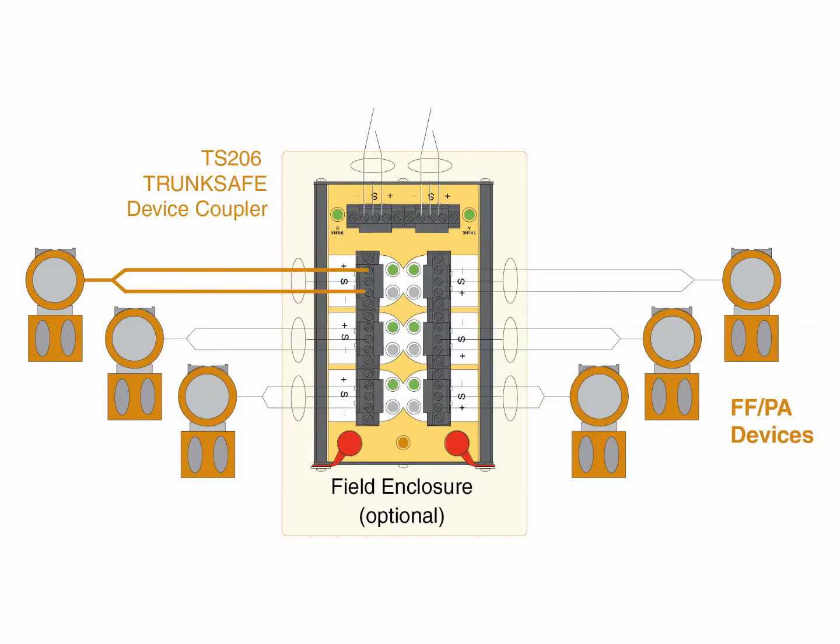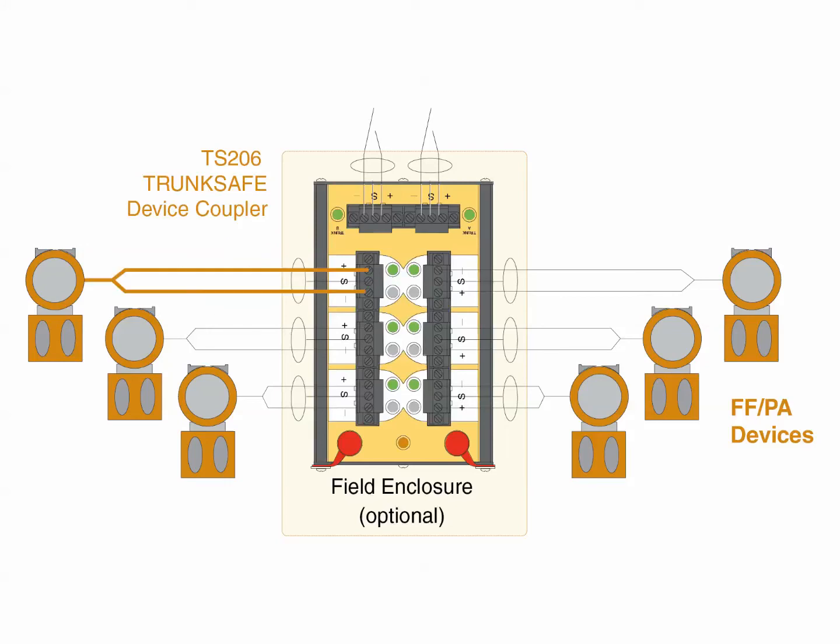This is a significant advantage over current-limiting designs which hold a fault permanently on the segment at a higher-than-normal current level. This can overload the segment power supply and lead to a segment failure.